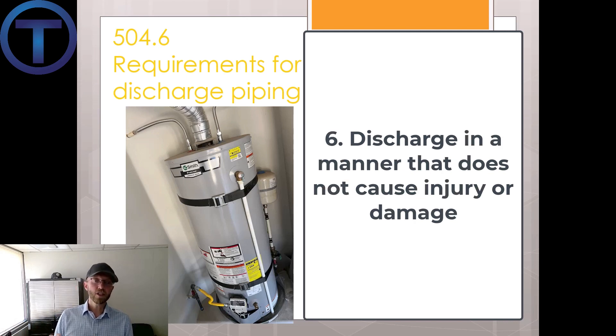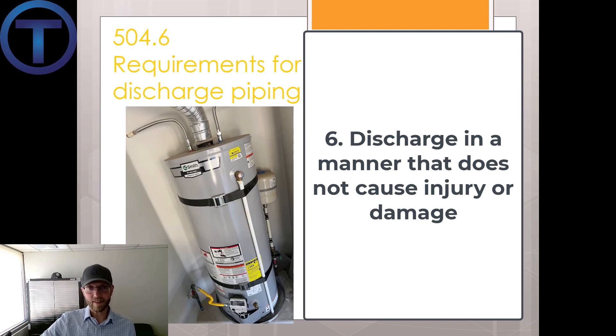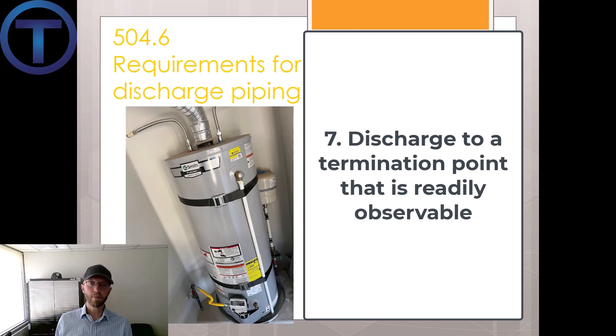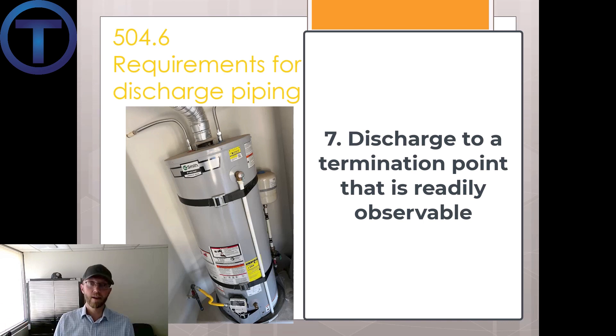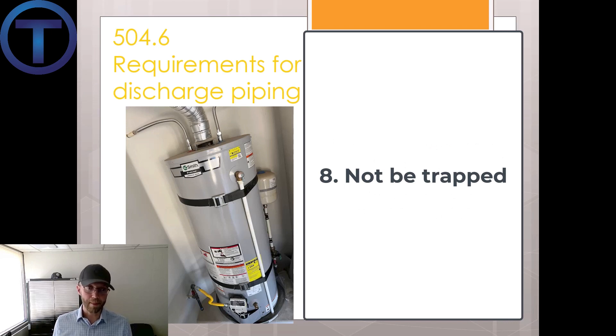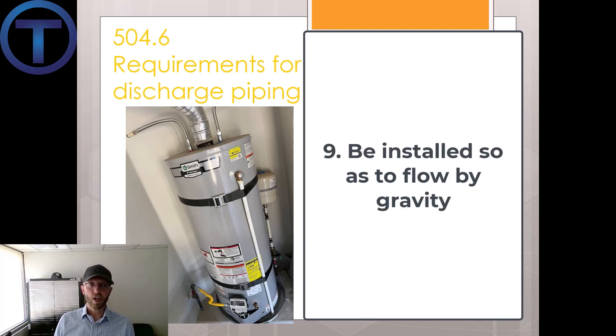Number six: it should discharge in a manner that does not cause personal injury or structural damage — so when approaching it while it's going off, you won't be hurt. Number seven: it should discharge to a termination point that is readily observable by the building occupants, because you should be able to see when it's opening and water is being discharged — that indicates a problem. Number eight: this discharge pipe shall not be trapped. Number nine: it shall be installed so as to flow by gravity.